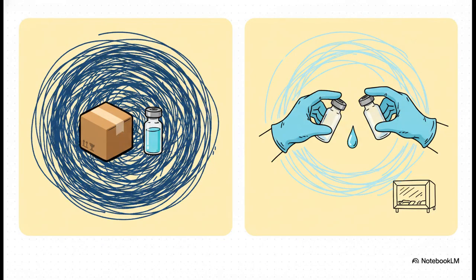Now, the math behind this level of safety is honestly fascinating. We measure it using something called a sterility assurance level, or SAL. Because terminal sterilization treats the final sealed product, it achieves an SAL of 10 to the negative 6. To put that into perspective, that means there is only a 1 in a million chance that even a single viable microbe survives. It's no wonder regulatory agencies like the FDA strongly prefer this method. But here's the catch. Some drugs, especially complex biologics, would be completely destroyed by the harsh, extreme conditions of terminal sterilization. For those sensitive products, we have to use aseptic processing, which does carry a slightly higher risk level of 10 to the negative 3.